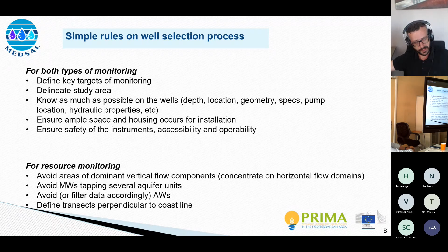Regarding the installation depth of groundwater level sensors, these pressure transducers that Andreas introduced before, we have some practical but essential rules. The basic goal is to place the sensor at a level that ensures that water will not drop below it. We don't want the sensor out of the water. We will take no data.